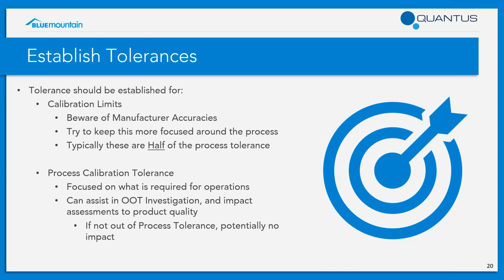So what we're typically going to recommend is that the manufacturer's tolerance is a really good place to start. But I'm saying beware of those accuracies because they might be too tight for your respective process. So as you're looking at what the manufacturer specifies, you're also going to want to keep it focused around the process that the instrumentation is actually measuring. In most cases, if you understand the process tolerance, we're going to recommend that your calibration tolerance is half of your process tolerance. So for example, if you have a -80 freezer that you validated to ±10 for uniformity as the process tolerance, we would recommend calibrating that with a tolerance of ±5.